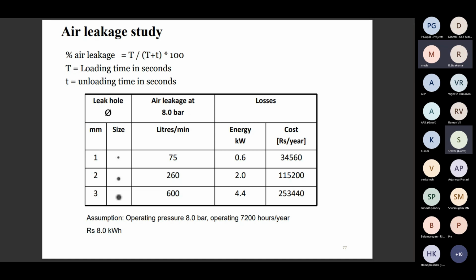During the air leakage study, if there is no air leakage, the compressor should be off for more than half an hour or 1 hour. But practically that does not happen. Based on the leakage quantity, the loading and unloading happen. Next.